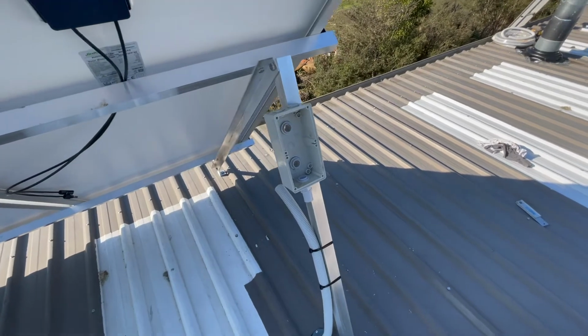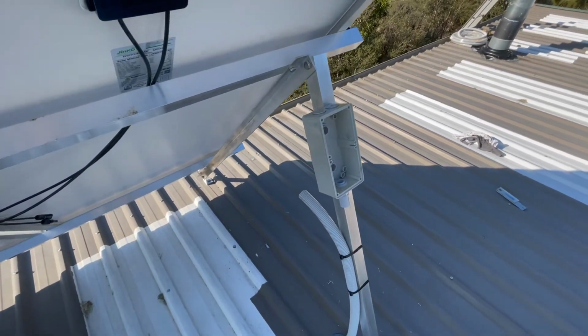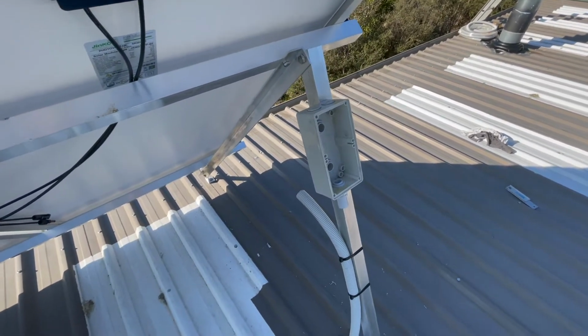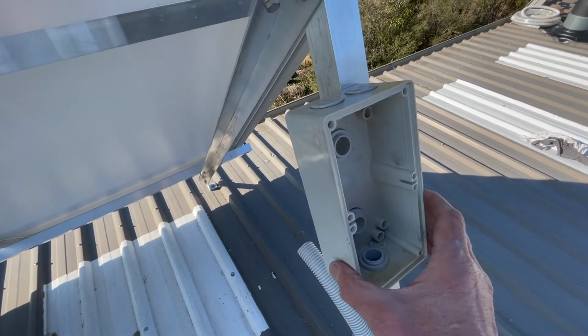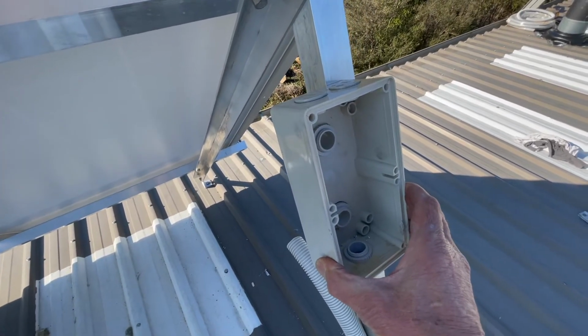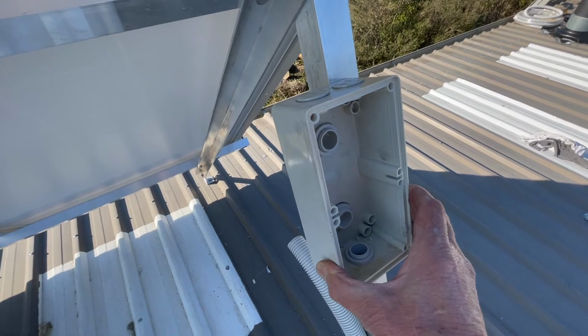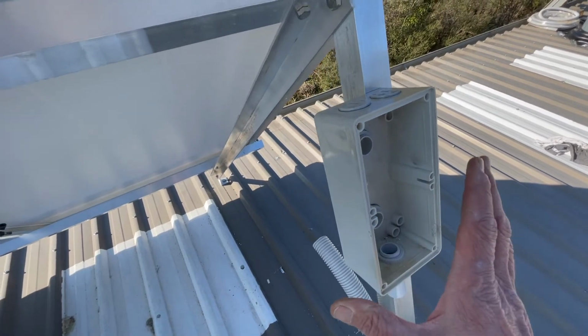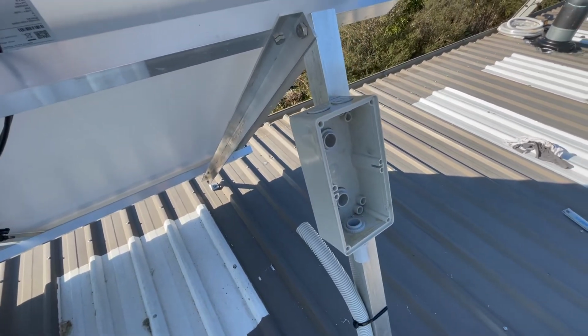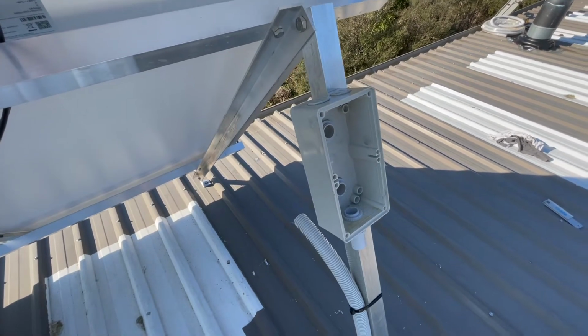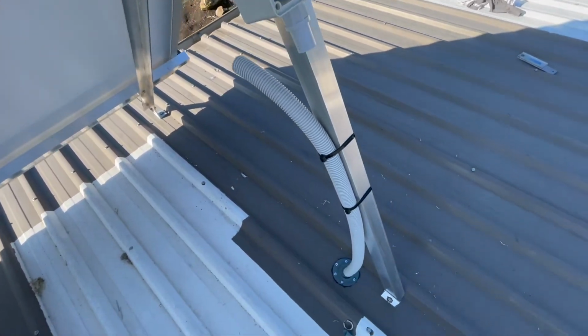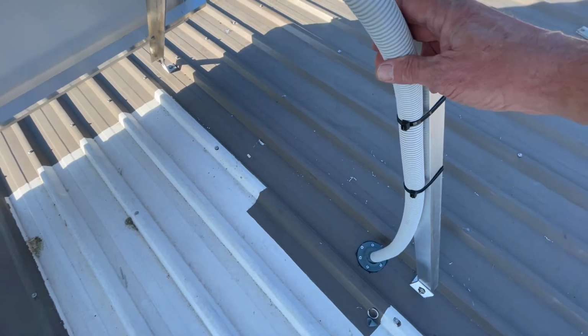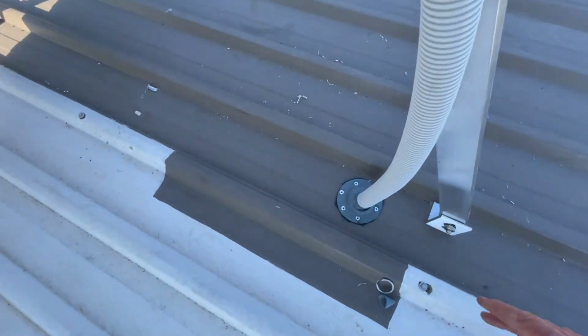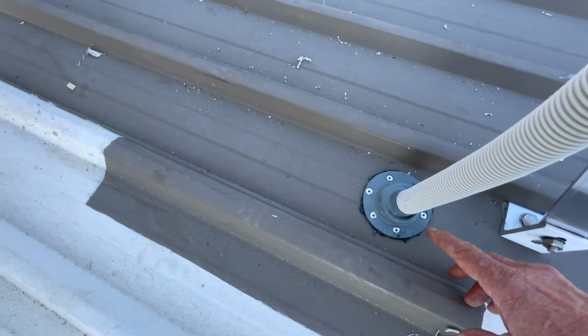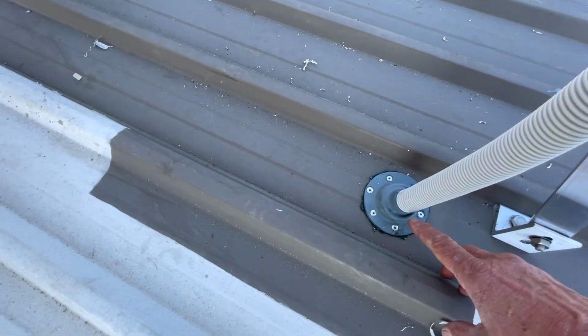Right, what I've done here is I've connected my outdoor enclosure for the solar array circuit breakers to a support leg. I've firmly riveted that on with aluminium pop rivet so there's no dissimilar metal corrosion, and that will take the circuit breakers for the solar, or the disconnect switch for the solar array. I've brought my 25mm conduit up through the roof using a device called a Dektite, which I've sealed to the roof using roof and gutter silicone.